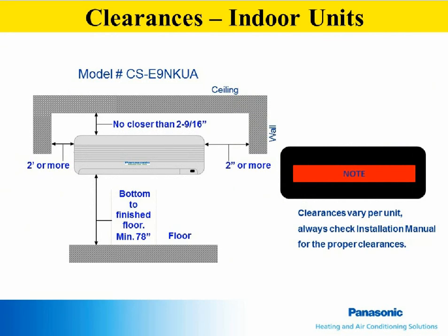Also take cleaning and service into consideration when selecting a location for the indoor unit. In this example, the minimum bottom clearance is 78 inches. If the unit is installed too low, hot or cold air can recirculate through the unit, causing it to think that it is satisfied. It can also cause the coil to become too hot or too cold and trigger the compressor to slow down to prevent freezing or high pressures.